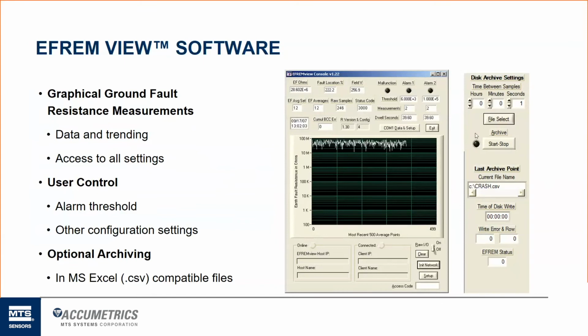Then on the right-hand side, you can see the disk archiving setup that allows the user to start archiving the data, and it will export that to a Microsoft Excel .csv file, so they can look at that data over a much longer period of time. We would probably suggest they do that once that initial ground fault or warning alarm comes in. They don't need to do that all the time. What they're utilizing is that 4 to 20 current loop output. That's the trending feature they're most concerned with monitoring.